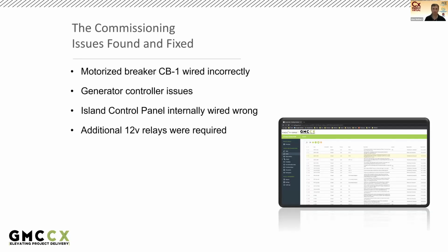For this project and all the projects, we used Facility Grid to track the issues, collect responses, and close the items that we found. Here are some of the issues that we found and we fixed. The first one is that the utility motorized breaker CB1 was wired incorrectly with the non-export relay due to drawings being incorrect.